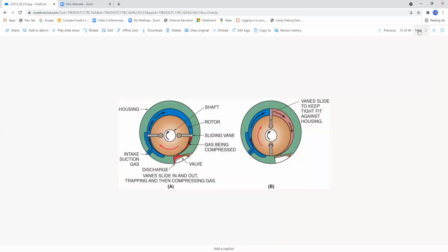Okay, here we have an example of the rotary compressor. This is going to be found on page 1074 under figure 36.23. This is, of course, your housing. This is your shaft. Notice that we have this lobe or rotor, which is in an offset formation, and refrigerant suction gas is taken in here. Then this thing moves, and as it moves, it takes this gas, narrows the channel, and increases the temperature and the pressure.